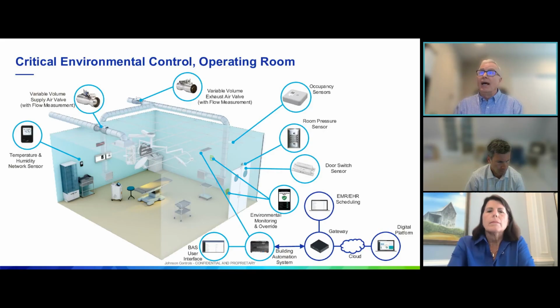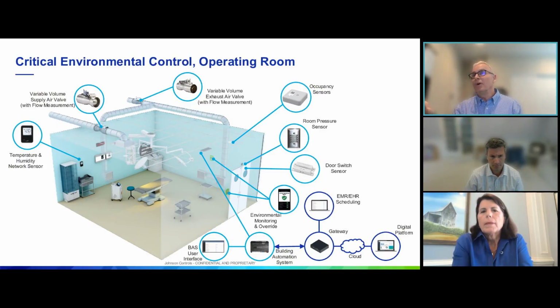And then talking real quickly about the air horsepower, or the energy that we're consuming within that space. Well, this is very heavily conditioned air, and many hospitals are running these rooms 24/7 because they're concerned about that resilient side of it. If they scale it down or turn off that area, how are they going to get back up into those conditions? And that's what 90.1 is addressing, saying that if you're not using that space, you really need to scale that back.